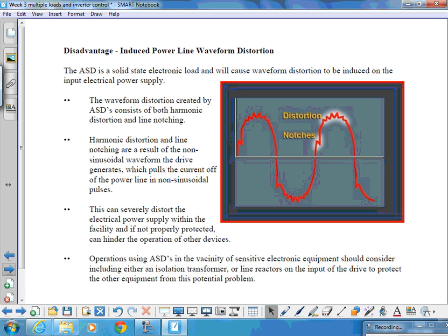Induced power line waveform distortion. A solid state electronic load causes waveform distortion to be induced on the input electrical power supply, which is effectively the national grid. Waveform distortion created by ASD's consists of both harmonic distortion and what's called line notching. Harmonic distortion and line notching are the result of the non-sinusoidal waveform the drive generates, which pulls current off the power line in non-sinusoidal pulses. So if the voltage being supplied is non-sinusoidal, the current it draws will also be non-sinusoidal. This can severely distort the electrical power supply within the facility, and if not properly protected, can hinder the operation of other devices.